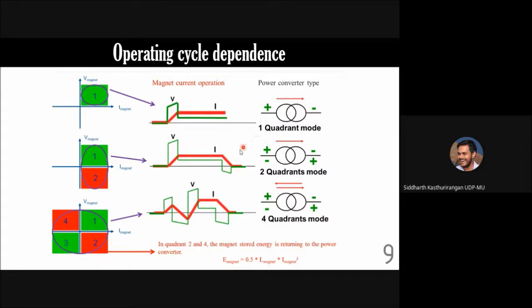The beam transport may require this to ramp down at this speed. So if you need to be able to ramp down at this speed, then you need the voltage to go negative. Similarly, if you want the current to change in the negative direction, then you need a power supply for which both negative voltage as well as current is possible.